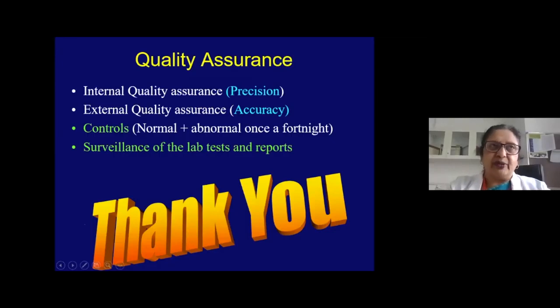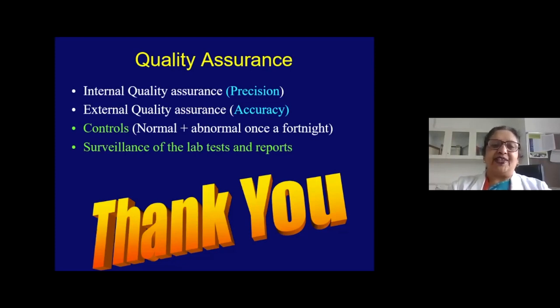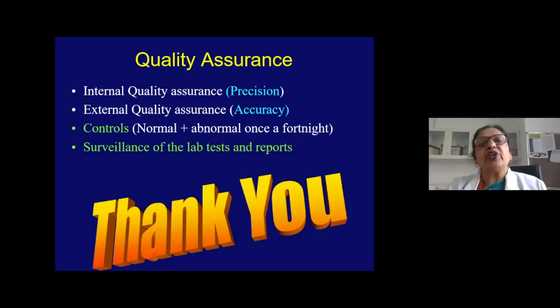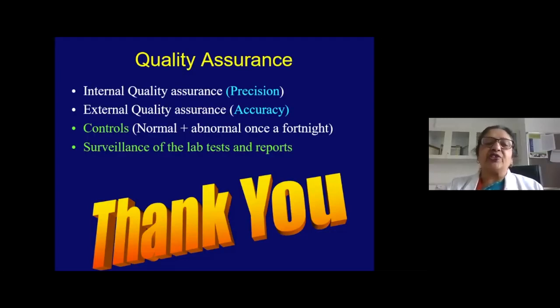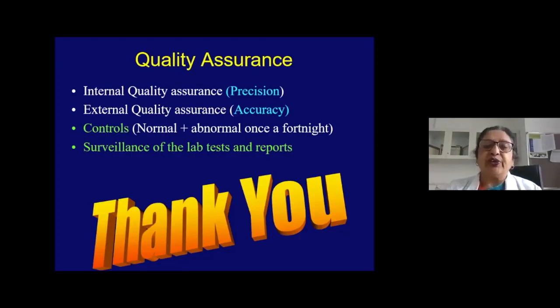Point-of-care tests add value in emergency settings but cannot replace PT/APTT. It is very important to ensure good quality assurance — both internal and external. Regular controls should include normal and abnormal controls; a low control can be run once a fortnight to maintain regular surveillance of the lab and ensure correct reporting. Thank you all for your patient attention.